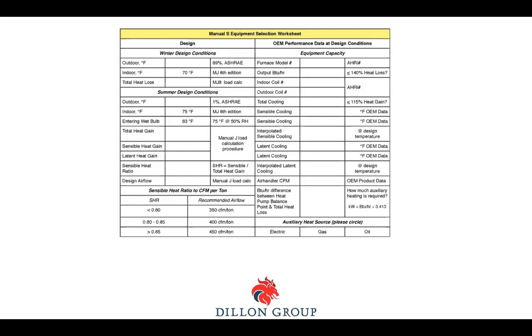So the HVAC contractor and I designed a system for that, because we knew the homeowner was going to finish it out himself, and then they're going to call and complain that the HVAC system didn't work. So all that happened, and we were able to just ramp up the dip switches and get it back to the speed, because I did two load calculations. And I said, well, let's get this piece of equipment, slow it down to this, and then it'll satisfy the load when the guy finishes out in a very crappy way, which he did.